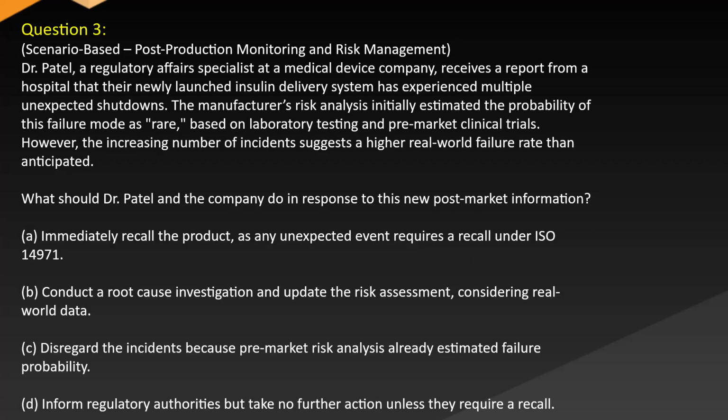Question 3. Scenario-based. Post-production monitoring and risk management. Dr. Patel, a Regulatory Affairs Specialist at a medical device company, received a report from a hospital that their newly launched insulin delivery system has experienced multiple unexpected shutdowns. The manufacturer's risk analysis initially estimated the probability of this failure mode as rare, based on laboratory testing and pre-market clinical trials. The increasing number of incidents suggests a higher real-world failure rate than anticipated.